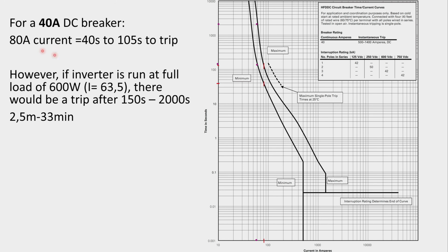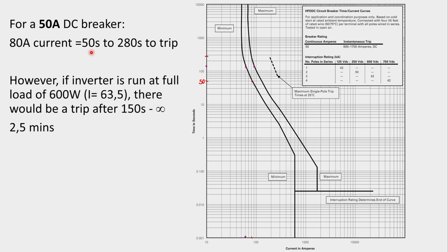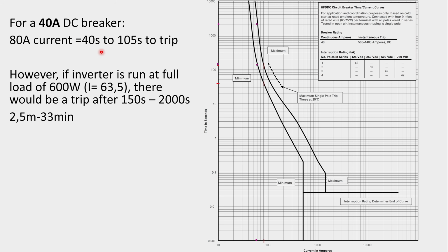So now here's a 40 amp circuit breaker. I also want it to trip at 80 amps. Now notice that the tripping time has reduced. It was 50 seconds to 280. Now it's dropped to 40 seconds to a maximum tripping time of 105. Notice how the curve is now more towards the lower current. But now, if the inverter was run at a full load of 600 watts, the unit will trip between 2.5 minutes and 33 minutes.